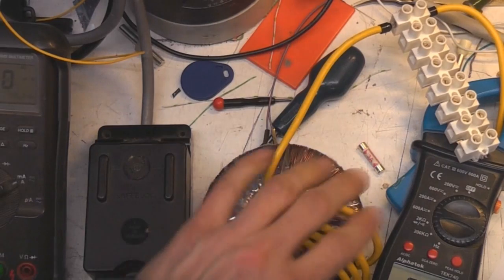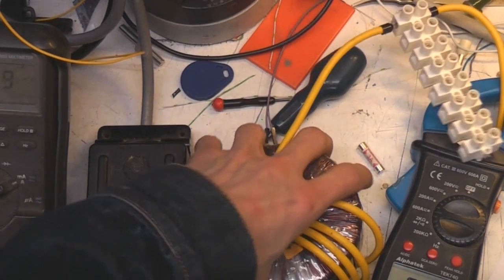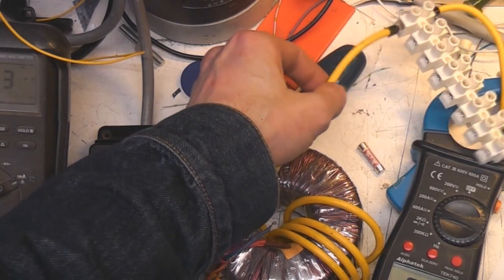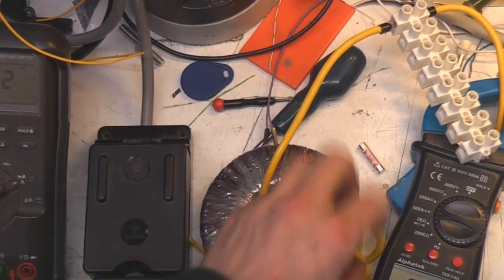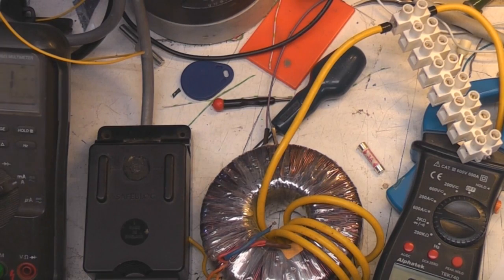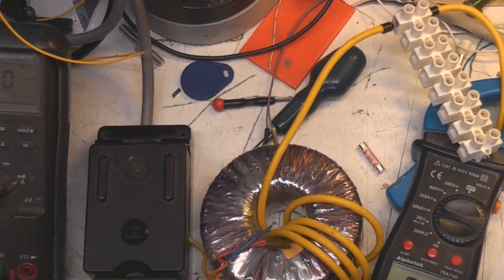Obviously, this wire is actually really hot just in those few seconds. So this is only suitable for short-term tests, unless you use much thicker wire, and that's almost too hot to touch just after those few seconds. So that would start smoking fairly quickly. It's not really rated for 300 amps, that cable, but it will do the job for the moment.